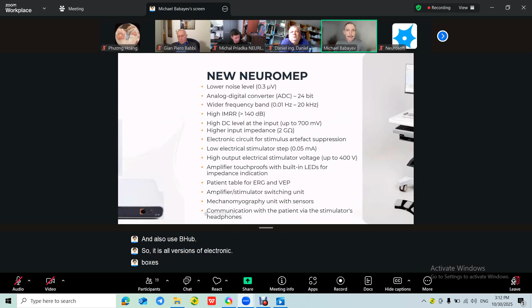Another type of stimulator unit is NeuroMep without E. It differs from the previous one in that it doesn't have a second electrical stimulator, this box. All other stimulators, auditory and visual stimulators, are inside this box, but this box doesn't have a second electrical stimulator. And the third version of the stimulator unit is the stimulator unit NeuroERG. It differs from the previous one in that it has only visual stimulators, only the goggle stimulator, pattern stimulator, Ganzfeld stimulator, and penlight stimulator, and also a USB hub. So that is all the versions of the electronic boxes.